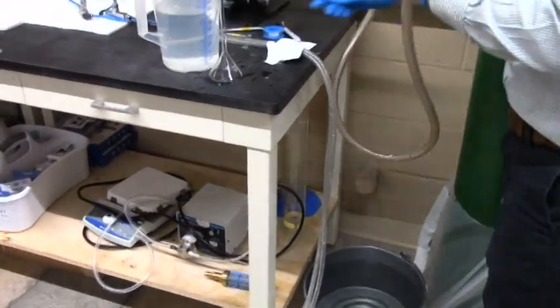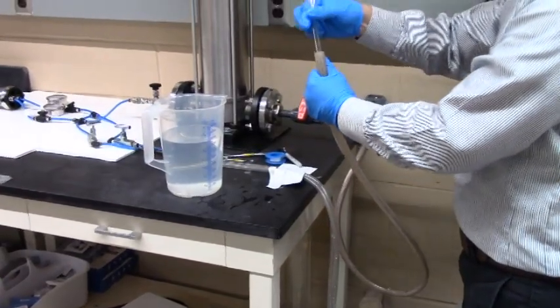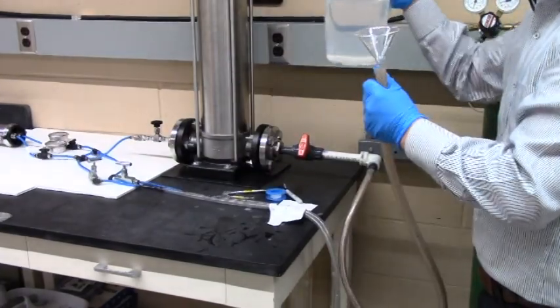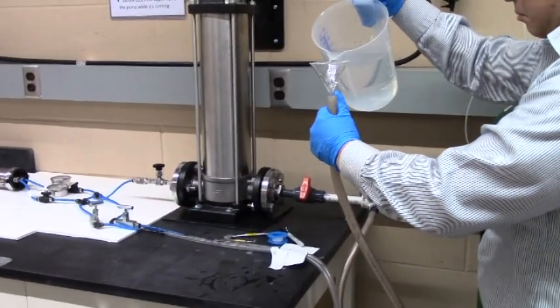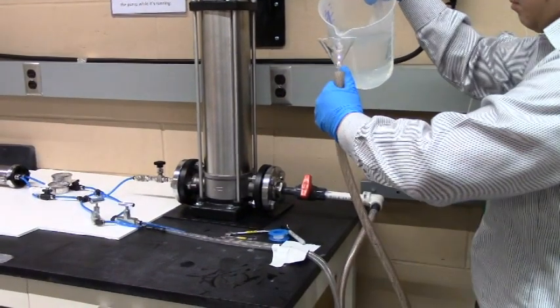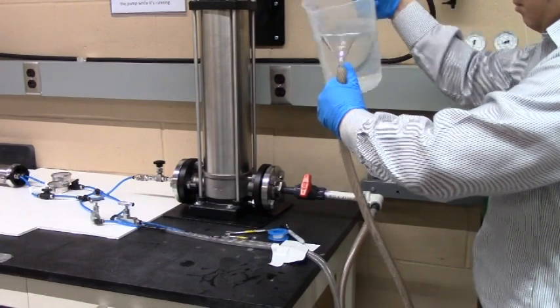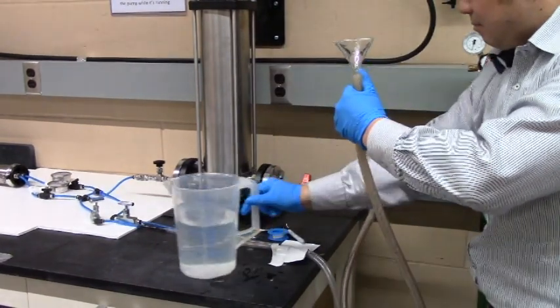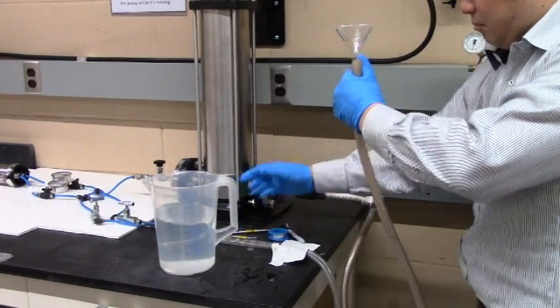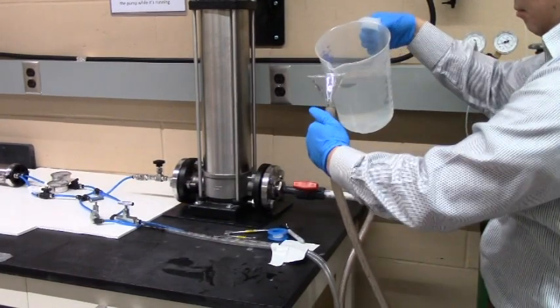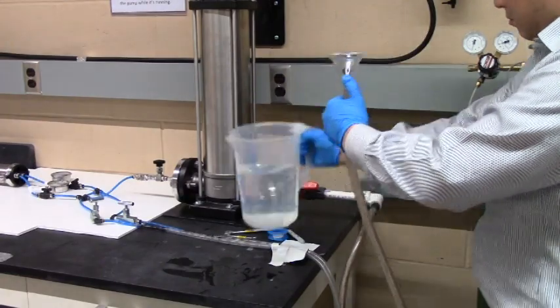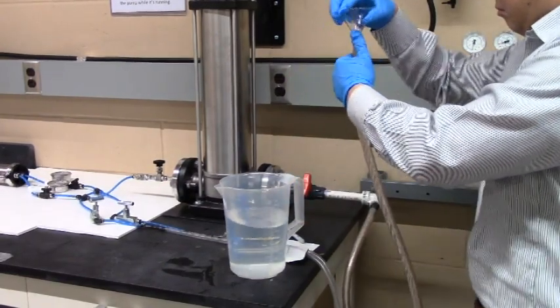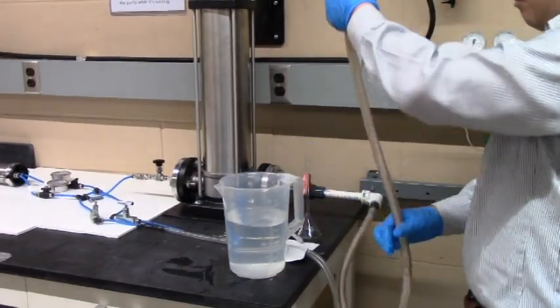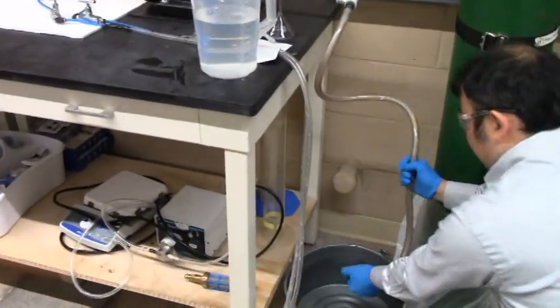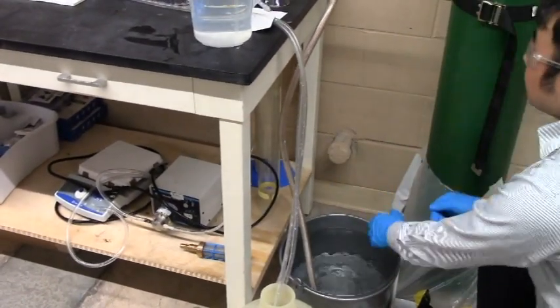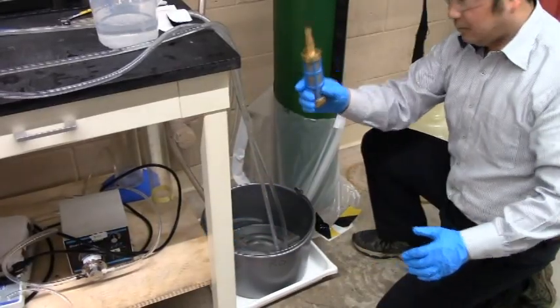Hold the open end of the centrifugal pump suction tube at the height of your face. Fill the tube with water using a funnel. Open the pump suction valve and air bubbles may come out of the tube. Then add more water to fill the tube again. Close the suction valve. Close the opening of the suction tube with your thumb. Bring it to the bucket, submerge it underwater, and then release your finger to keep air out of the tube. Keep the opening of the suction tube submerged.